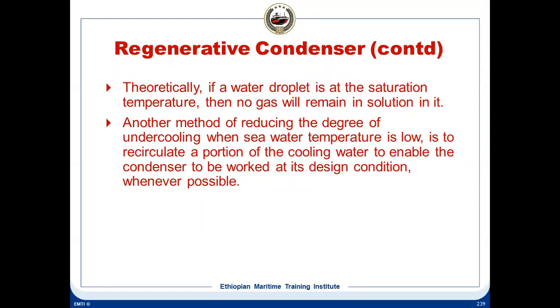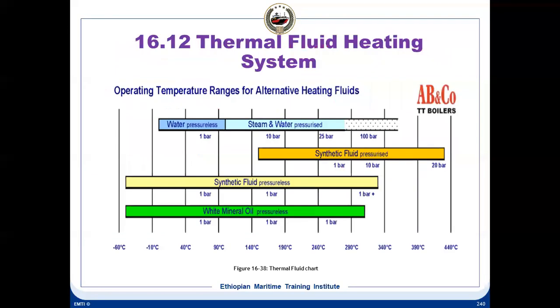This recirculating idea we also have for your main engine jacket water, main engine lube oil, etc., in very, very cold conditions. Part of the seawater is recirculated so that the jacket water is not undercooled, and similarly your lube oil also is not undercooled. The same theory works here.